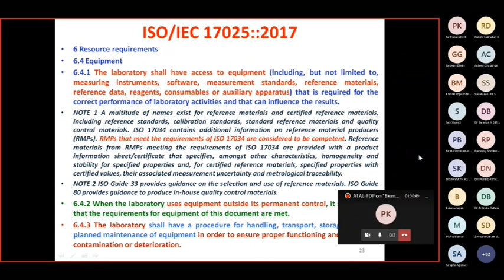Similarly, when something is taken for preventive maintenance or for any service by the OEMs, when it comes back to the laboratory for service, ensure they are in good shape. You may have to do some preliminary checks, have a dummy run or a test run to ensure they are performing as per the plan, as per the requirement, before you start doing the actual work. Similarly, evaluate the process capability of your equipment and instruments periodically and keep records.